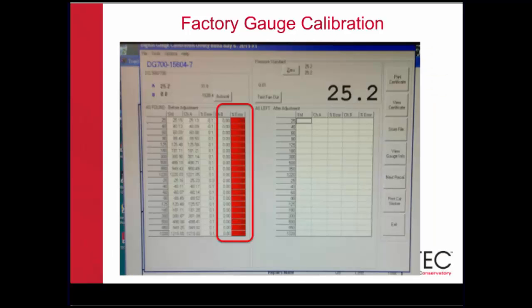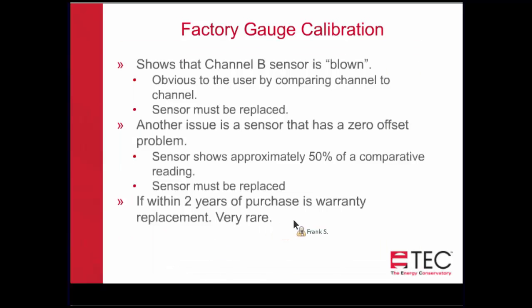Now I apologize for the fuzziness of this image, but the intent is to show you that calibration of gauge serial number 15604 has channel A actually is really quite good, but channel B doesn't have any values. So what that means to us is that the pressure sensor on channel B, we sometimes refer to it as being blown or just broken. So when we see that, we have to go in and change that. So the sensor must be replaced.